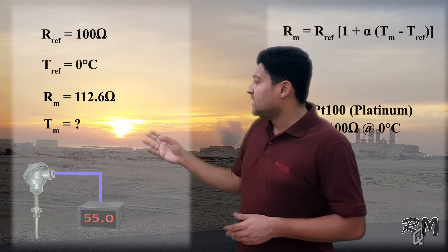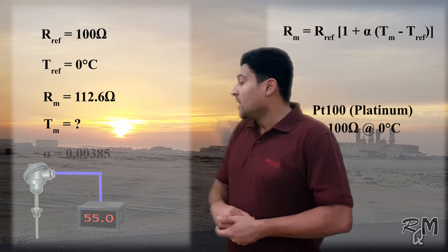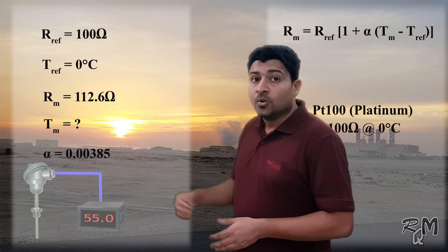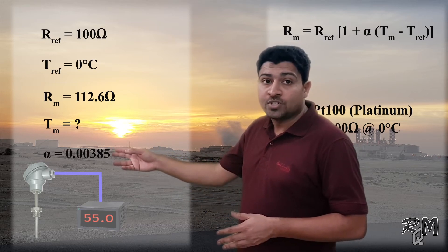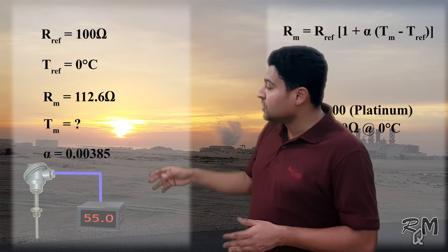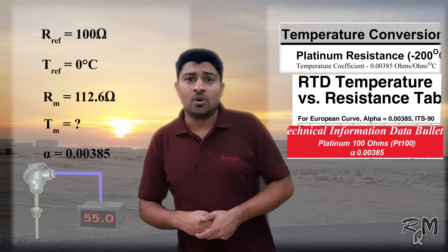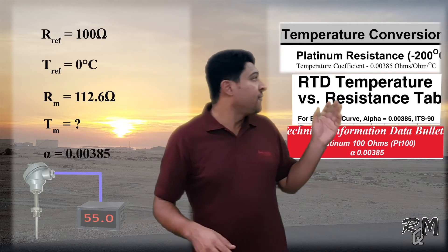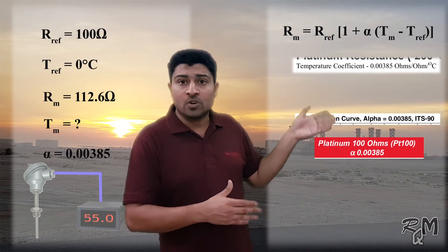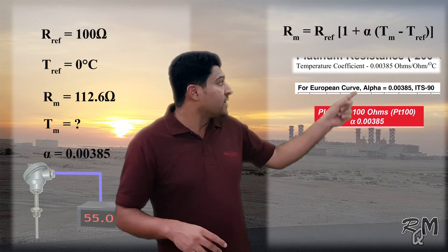The measuring temperature — this is what we have to find through this equation. The alpha is a very important value. This is the temperature coefficient and it is equal to 0.00385. You can find this alpha value on different manufacturer RTD conversion tables. You can see here, it is on the top.